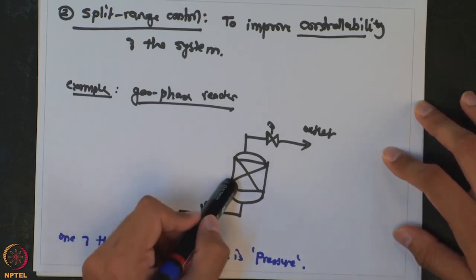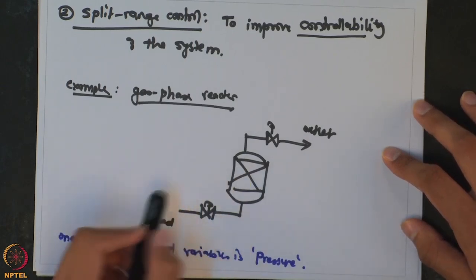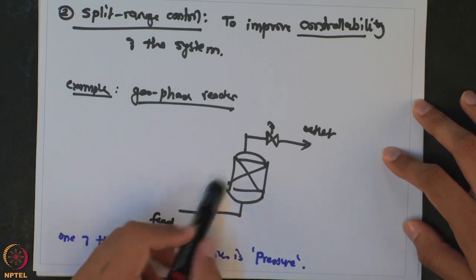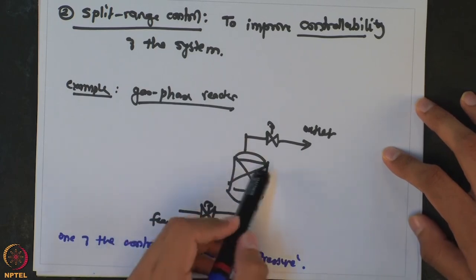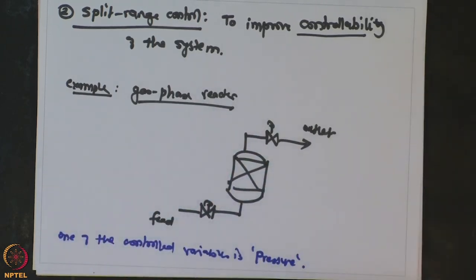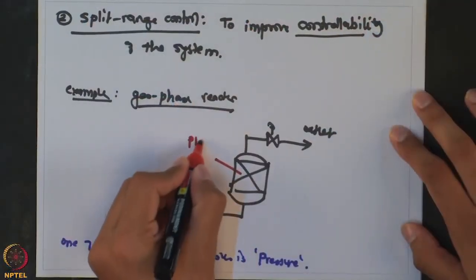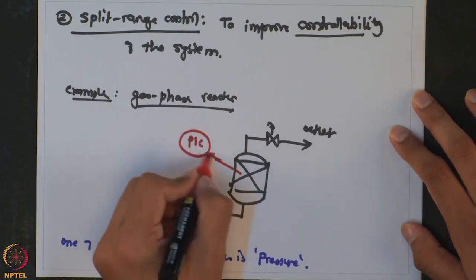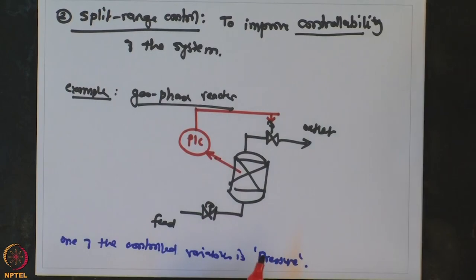Typically when selecting pairings between input and output, you want minimum effect of pressure or inventory control on the actual operation — the reaction. You typically use the feed valve to control the throughput, so you would want to control this pressure using the outlet valve so it does not affect reaction productivity.